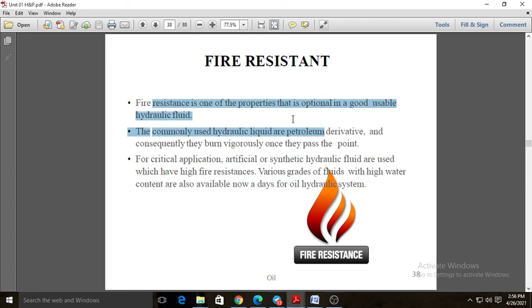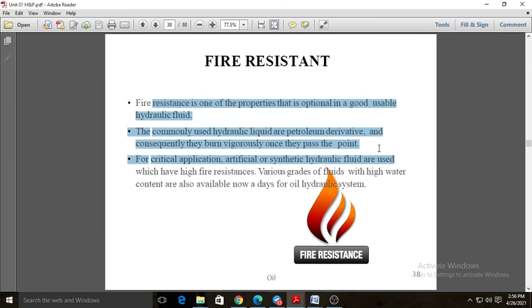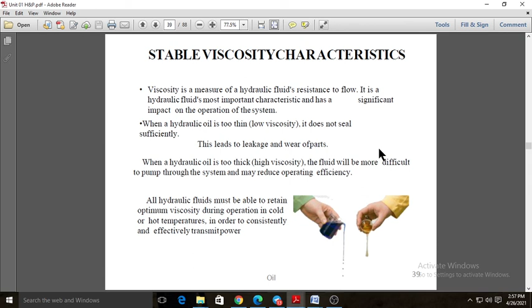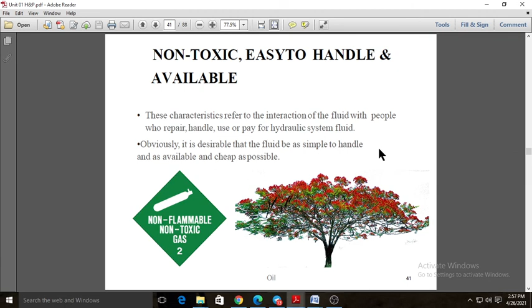Then fire resistance. Fire resistance is an optional property in a good hydraulic fluid. The commonly used hydraulic liquids are petroleum derivatives, and consequently they burn vigorously once they pass the flash point. For critical applications, artificial and synthetic hydraulic fluids are used. Then stable viscosity characteristics: as I already told you, viscosity should remain independent of temperature and pressure. It should prevent rust formation. Then it should be non-toxic and friendly to the atmosphere.